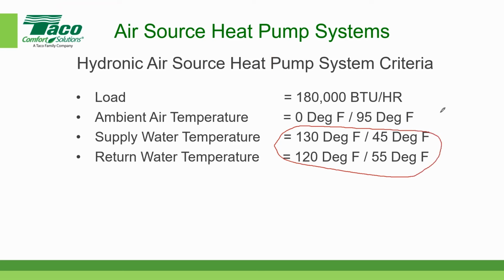10 degrees. Now, in a conventional hot water heating system, typically if you're using fossil fuels in modern hot water heating systems, the delta T can be 20 or 30 degrees. Some people have even designed them as high as 40, but the more common numbers are between 20 and 30. But in an air to water heat pump system, the water temperature delta is around 10 degrees for both the heating and the cooling. And when you do that, the GPMs wind up for the same capacity to be virtually the same GPM. Any questions about that? That's kind of a subtle thing, but it's an important piece. Nope.